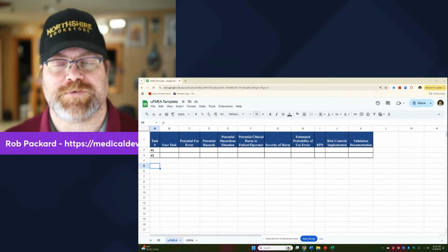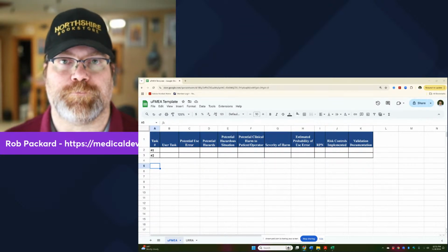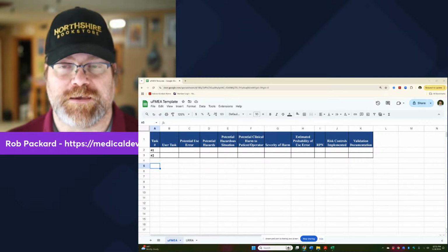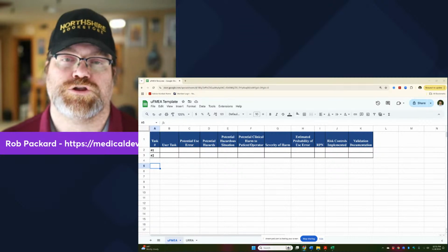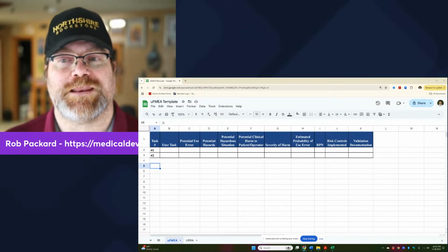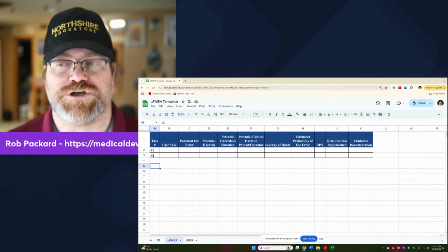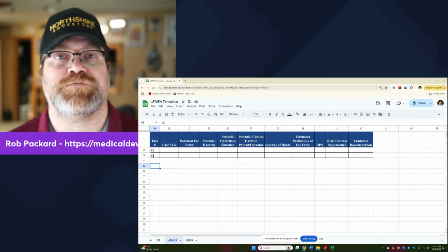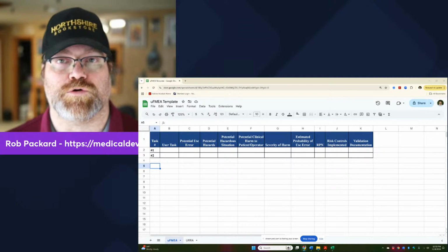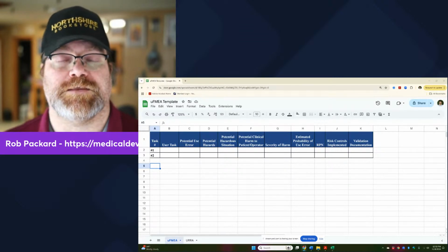The way it's typically done is you start with the instructions for use or user manual and go step by step through how the product is used. And you might have multiple use FMEAs for different use cases. You might create one use FMEA for the normal use of the product, but you might create a separate one for the reprocessing or cleaning and disinfection of the device. You might have another one for service of the device. You might even go so far as to create one for installation or maintenance of the device. Nothing wrong with that. That would be excellent if you did those things.